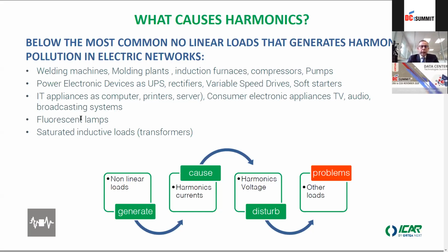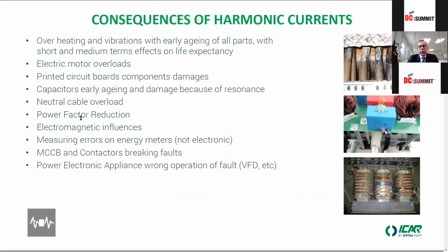So this will create troubles between the main line and load. It can create overcurrents that can burn some components, or overheat the cables, cause vibrations, and reduce the power factor, which also makes it impossible to absorb the total power of a power transformer that we have of, for example, 1000 kVA.